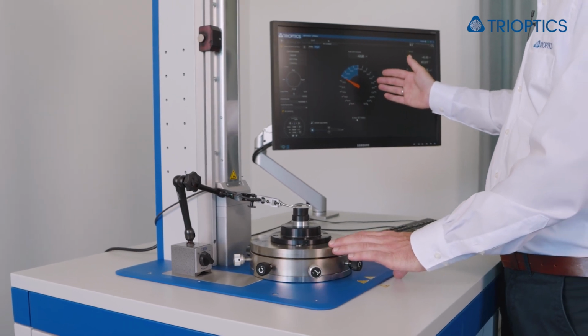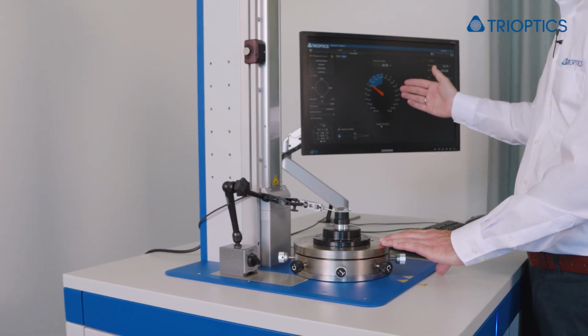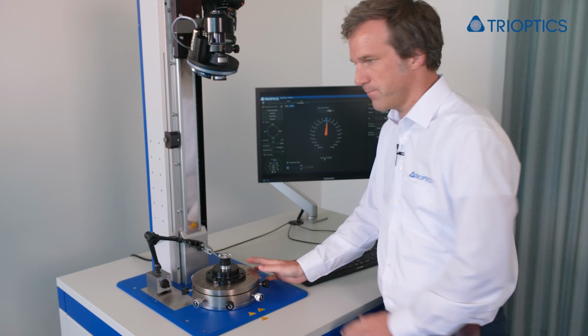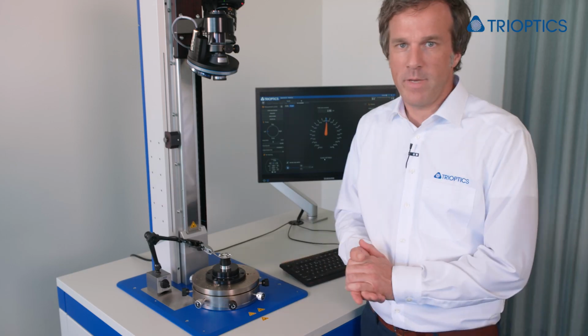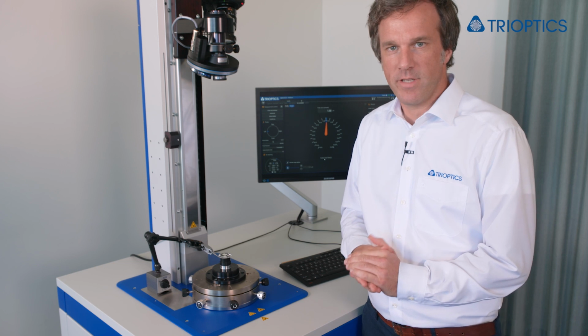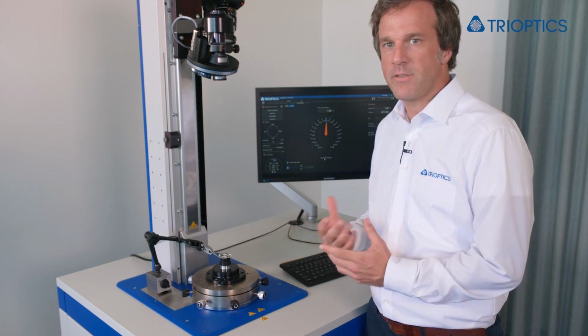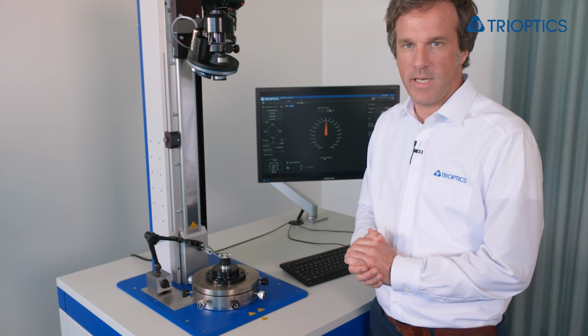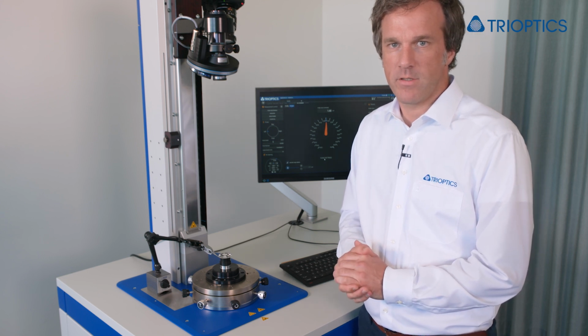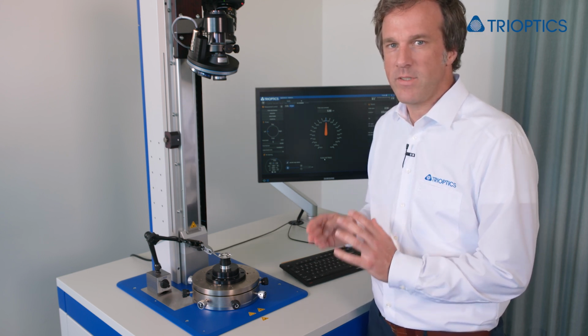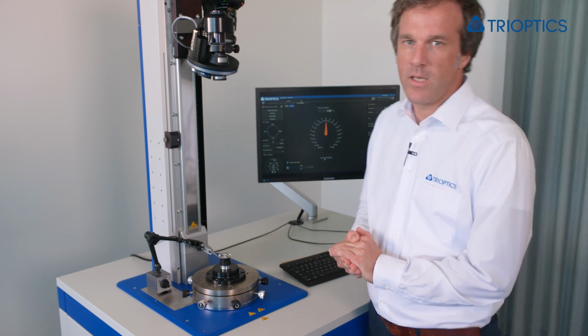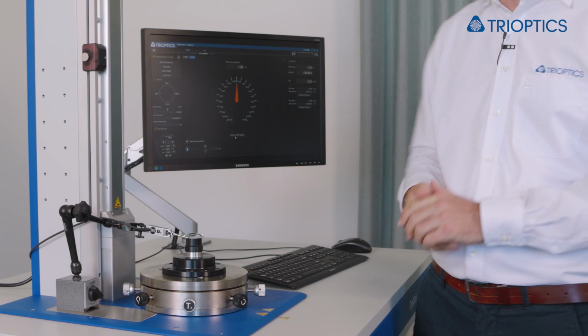In the workshop, the parameter you are mainly interested in is the center between the maximum and minimum value of this indicator. So you need to do some calculation to know where to level to center the lens barrel. In order to make sure that you really catch the data of a full revolution, we can also engage the motor drive and let the software control this rotation. But before, I will switch on the automatic scaling, which will make it a bit more convenient for the operator.